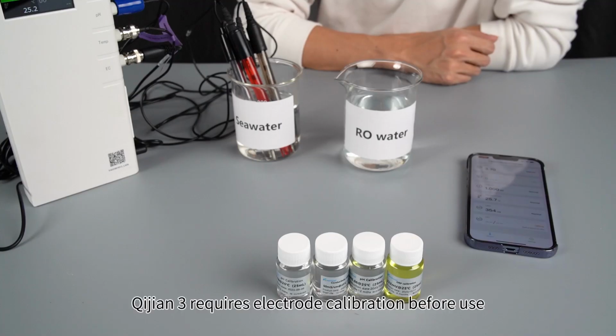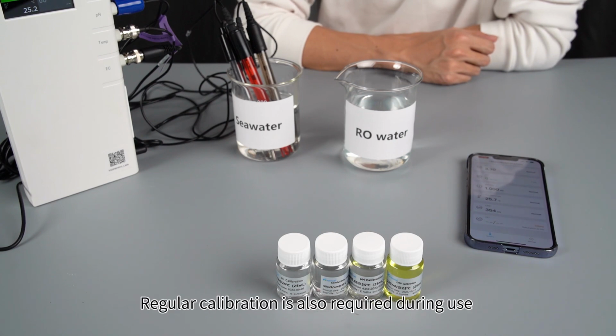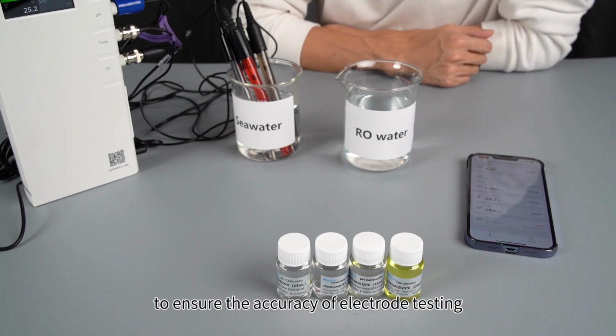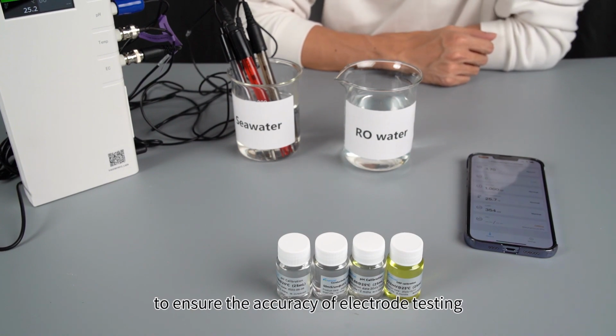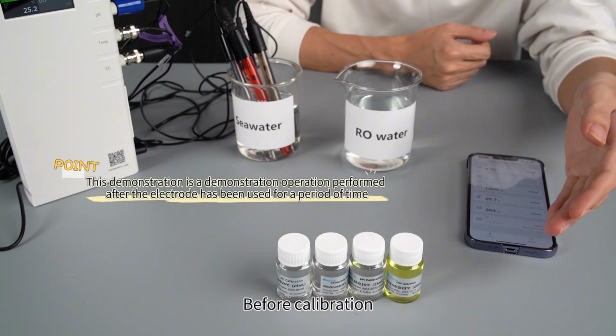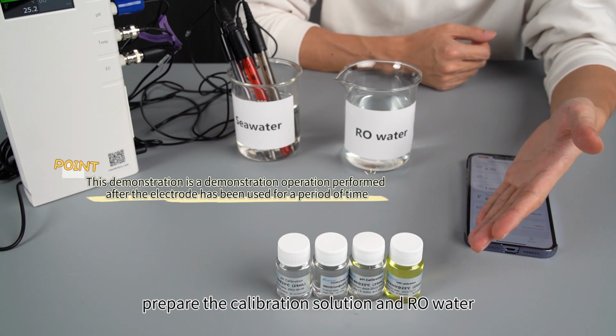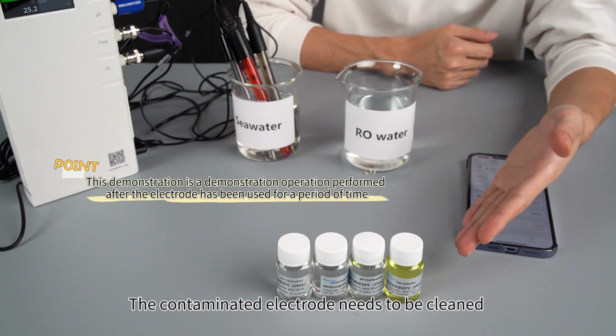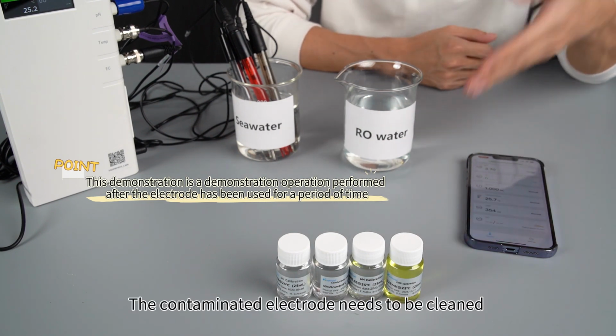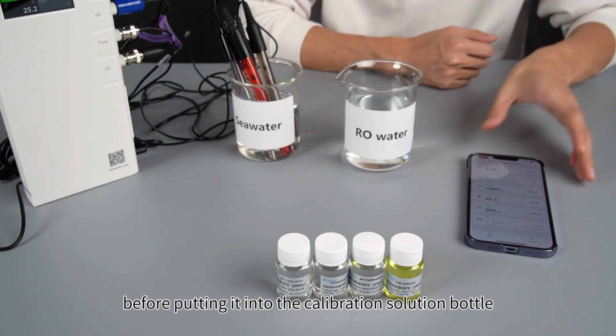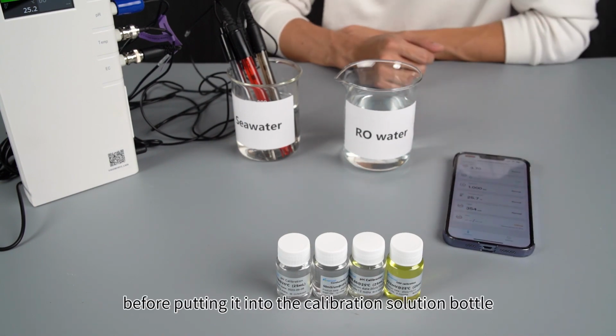QIJIAN 3 requires electrode calibration before use. Regular calibration is also required during use to ensure the accuracy of electrode testing. Before calibration, prepare the calibration solution and RO water. The contaminated electrode needs to be cleaned with RO water before putting it into the calibration solution bottle.